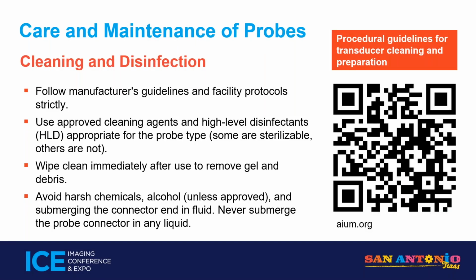And even that, I hate to pick on GE too much, but let's say 15 years ago, their manual said, do not use harsh chemicals and heat to clean your probe. And then they partnered with Trophon, which uses harsh chemicals and heat to clean your probe. And then they changed all of them, so it doesn't say that anymore. But the fact of the matter is, harsh chemicals and heat will cause damage to your probe over time. So I'm not picking on GE or Trophon because there are other manufacturers out there too.